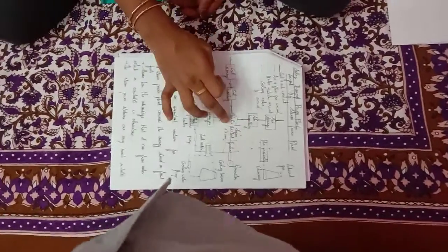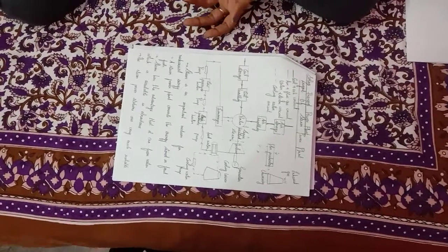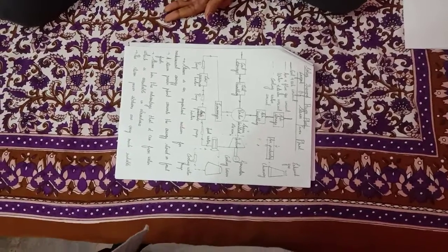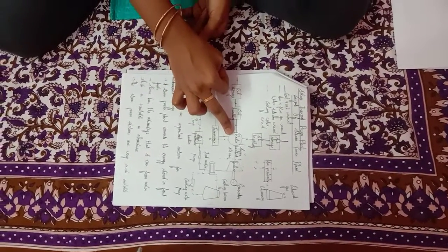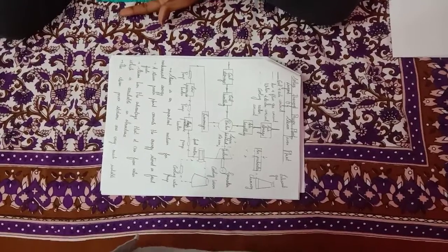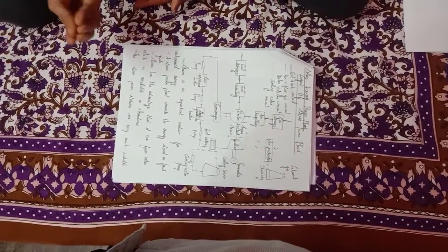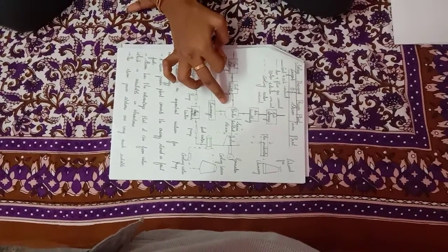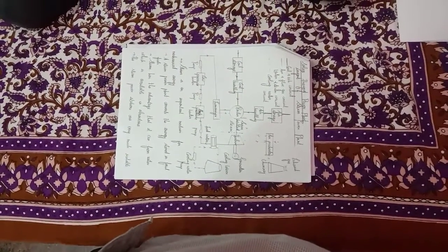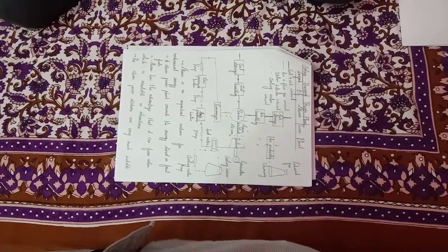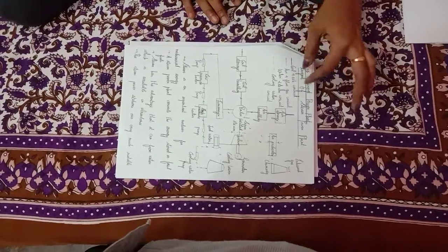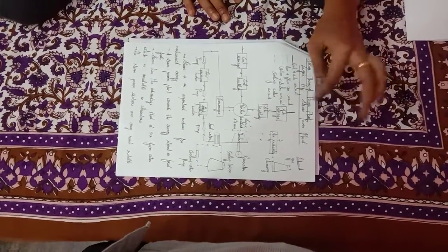The coal will be transferred to the boiler with the help of some equipment, namely grab bucket conveyor, screw conveyor and bucket conveyor. Using this equipment, the coal will be transferred to the boiler and the operations will start, and finally it results as ash storage. It will be removed with the help of ash handling equipment. Indian coal will produce about 30 to 40% ash in the layout of the steam power plant.